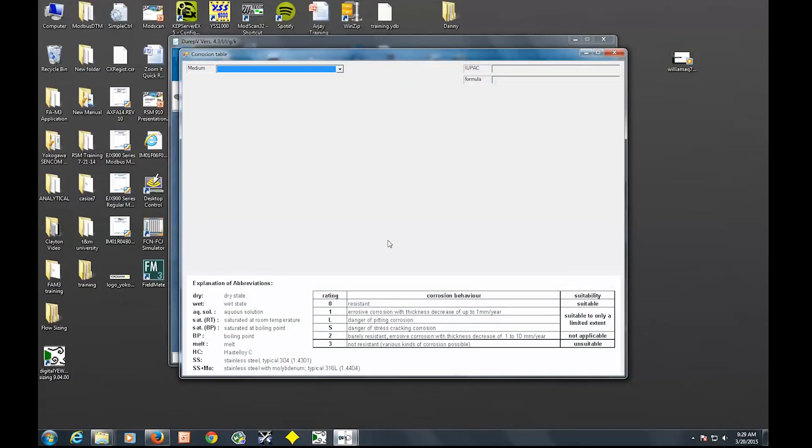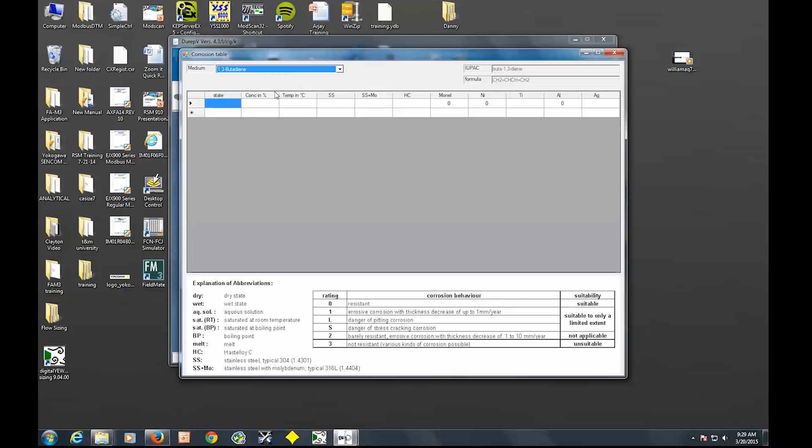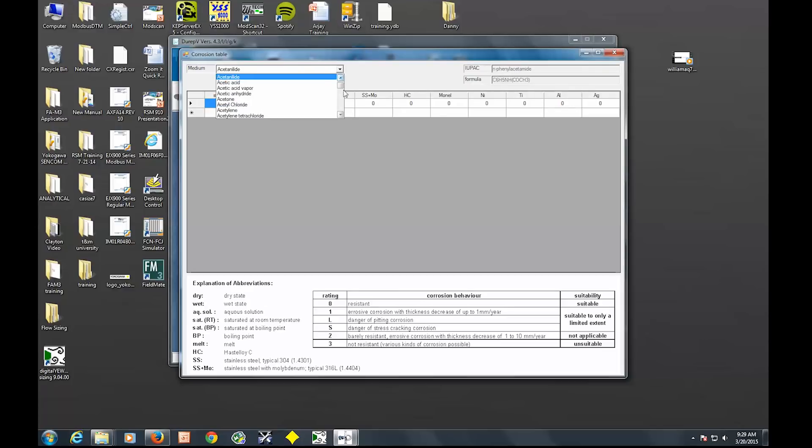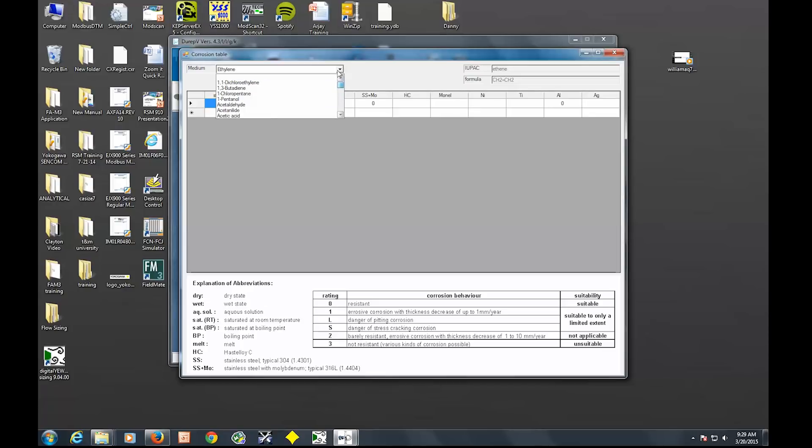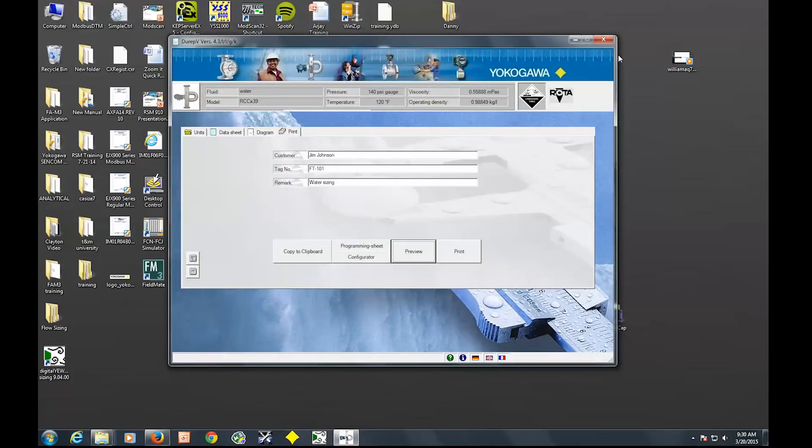So click OK. And then we have basically all the fluids and then a few more just known to be corrosive fluids and all their properties and what you can expect as far as if our meter is suitable or as far as our wetted parts. So stainless steel and Hastelloy are two wetted parts. And this kind of goes through the ratings. Zero is resistant and then three is not resistant, so we wouldn't recommend it at all. But this was this particular sizing was water, so we're not too worried. Stainless steel should do the trick. But just know that we do have a handy guide here if you need it if you're not measuring water.